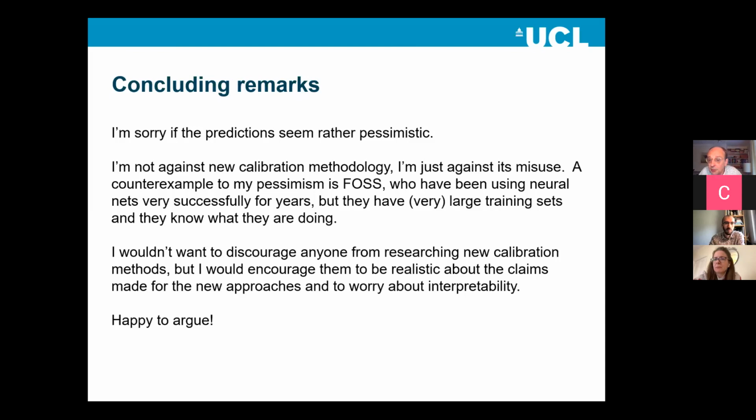There's a couple more questions which I can't see because they're running off. So: error of prediction obviously includes statistical error, but also instrument, operator error, temperature. Any idea how to distinguish? In other words, only validate predictions on samples that were properly taken. So the usual way, and I suspect most people pay lip service to it rather than actually do it, is that you can obviously look at whether the spectrum of the sample that you're about to predict looks like the spectra of the samples in the training set. And you can do that by things like Mahalanobis distance, things like plotting them in PC space. You could use the Mahalanobis distance on PCs or on PLS factors. And if it's more than a certain distance, then maybe you should worry about it. So yes, there are standard ways to do it. I suspect most people don't do it most of the time.